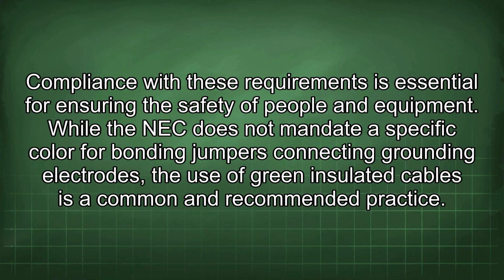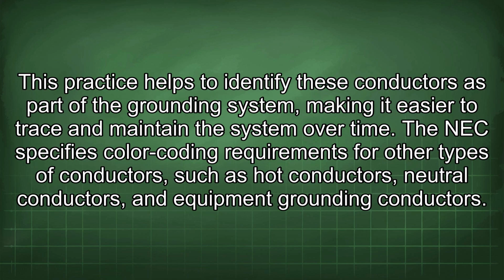Compliance with these requirements is essential for ensuring the safety of people and equipment. While the NEC does not mandate a specific color for bonding jumpers connecting grounding electrodes, the use of green insulated cables is a common and recommended practice.